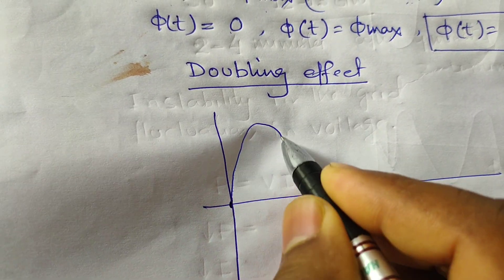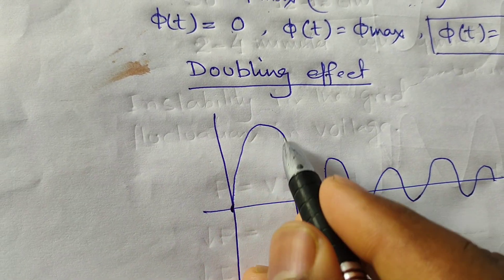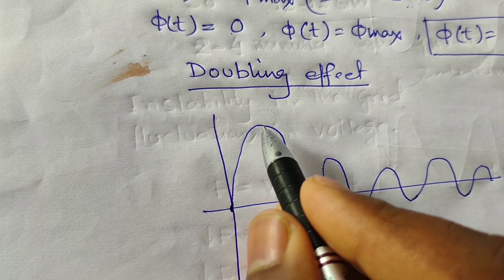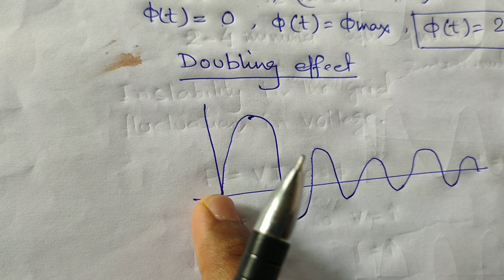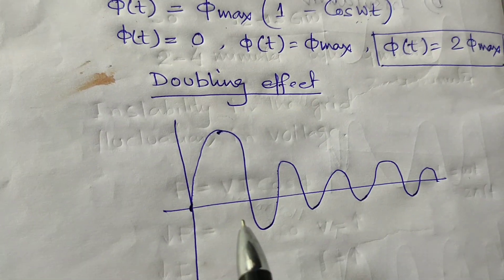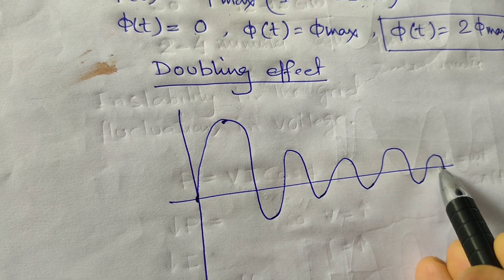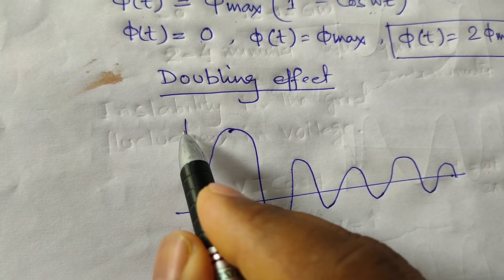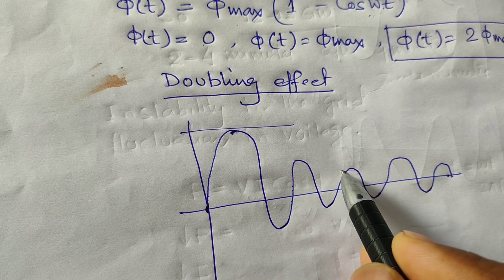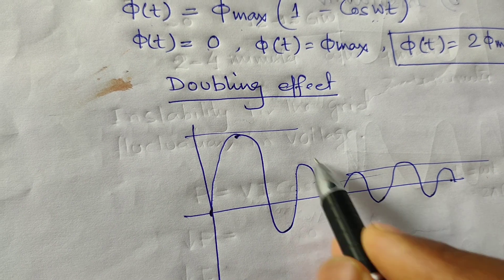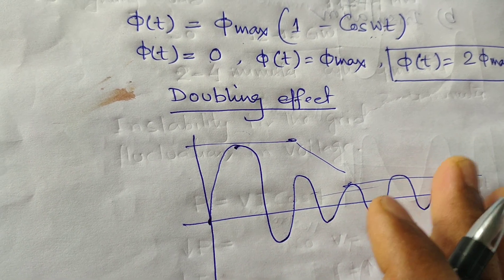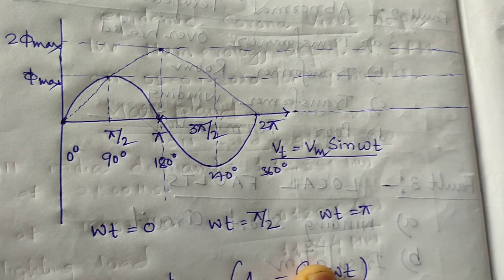When we switch on the transformer, the maximum flux is generated and a maximum peak current results. After reaching the saturation value, the current curve settles and the steady-state rated current is reached. The peak current above the steady-state value is the inrush current, also called the transient current. This peak represents the inrush or transient current.